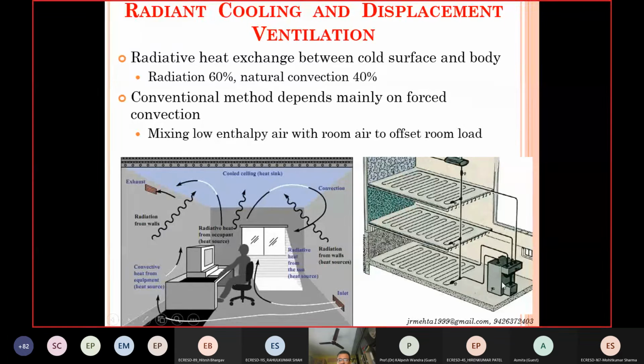And here is the scheme. This is the water chilling plant and the coils which are embedded into the floor or ceiling, which has lower temperature, which reduces the temperature of the ceiling, and by mode of radiation it cools the other entities in the conditioned space.